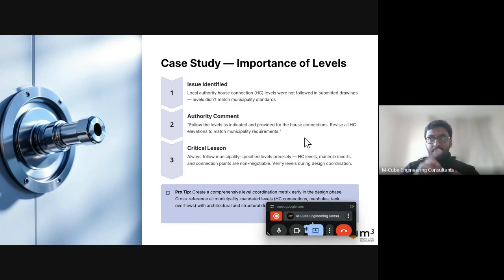Another important thing: in one of the projects I worked on, a CU park 4 and 6, the invert level was going very high, more than minus 1.2. In that case, try to ensure and check if the invert level can be reduced, whether you can reroute it a different way. If it's not possible, then you need a sump pit and submersible pump to be added.